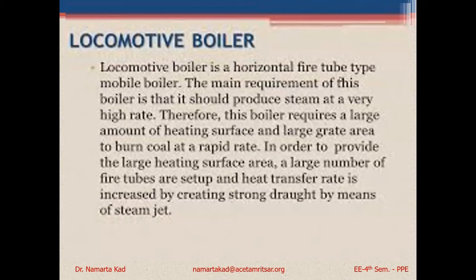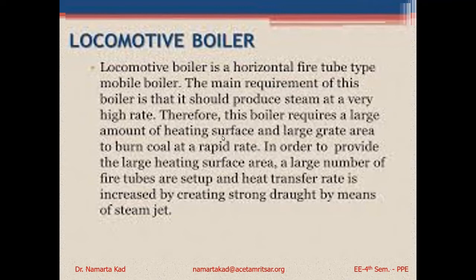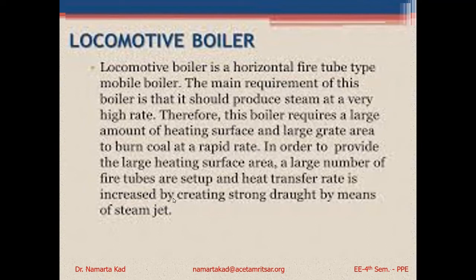The locomotive boiler is a horizontal fire tube, mobile boiler. Unlike the Cochran and Babcock Wilcox boilers which are fixed at a location, locomotive boilers are movable — they can move from one place to another. To produce steam at a very high rate, this boiler requires a large heating surface and large grate area to burn coal rapidly. A large number of fire tubes are used, and heat transfer is increased by creating an artificial draft through a steam jet.